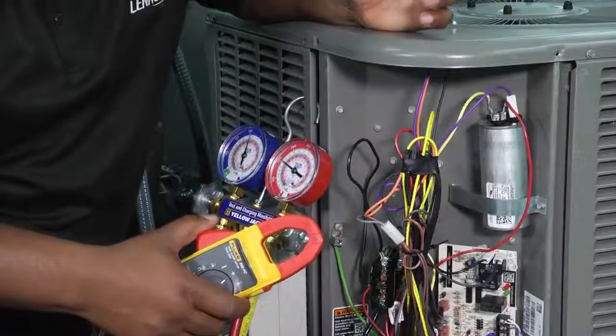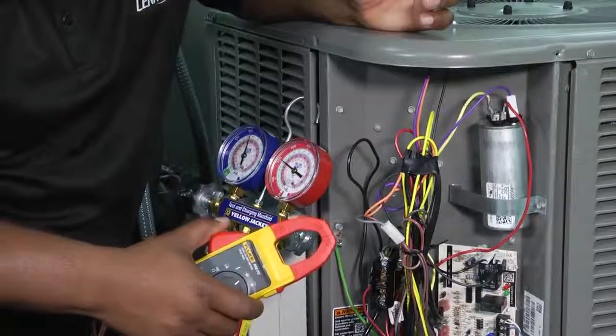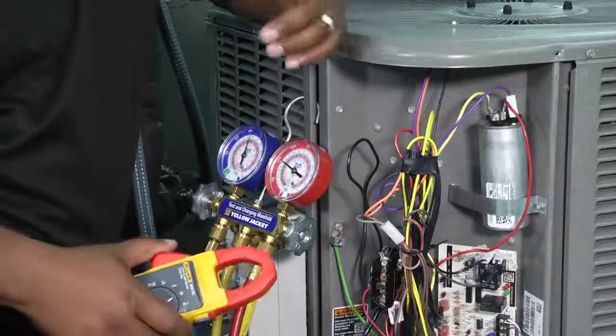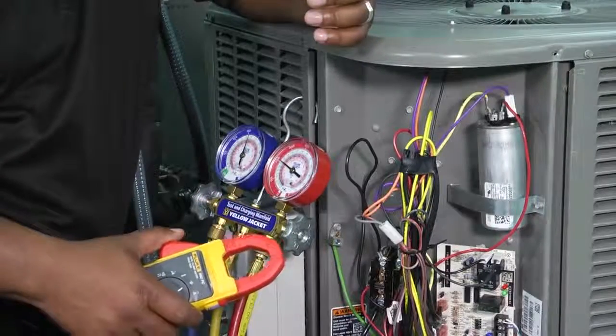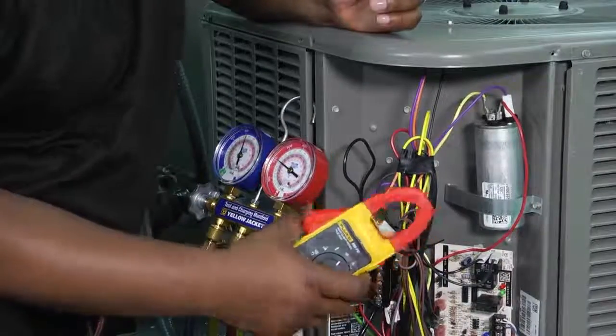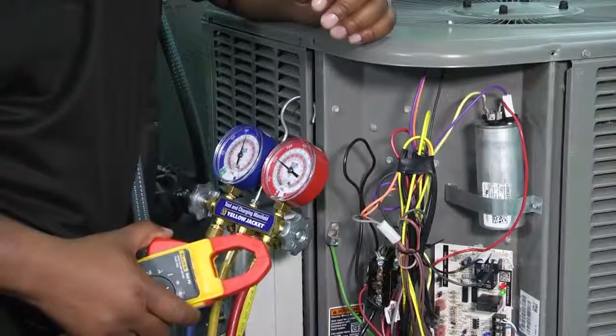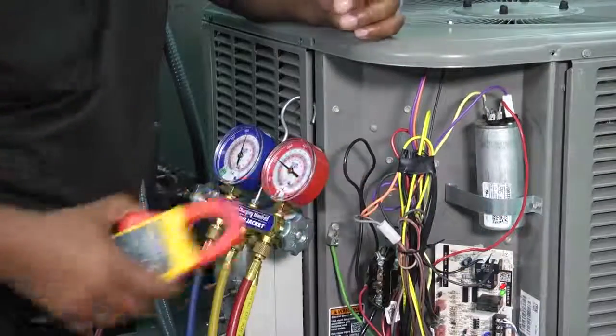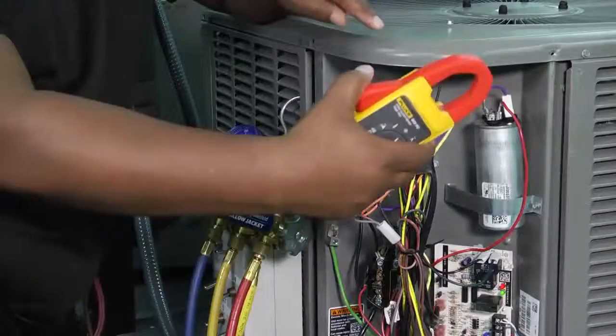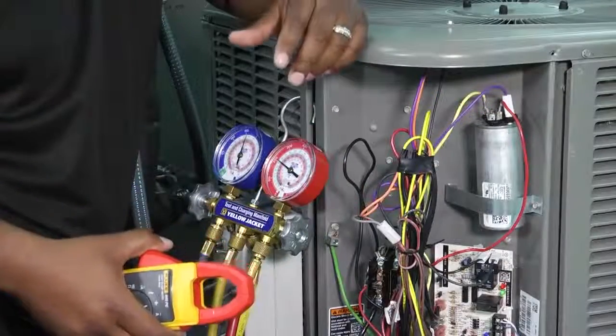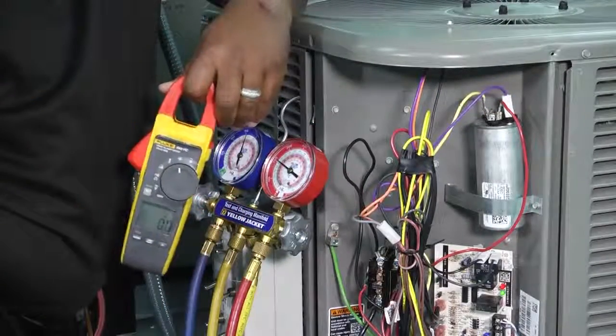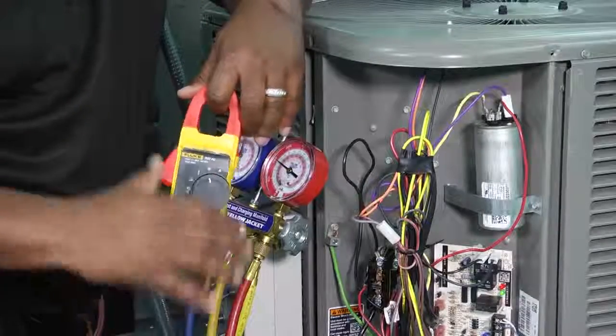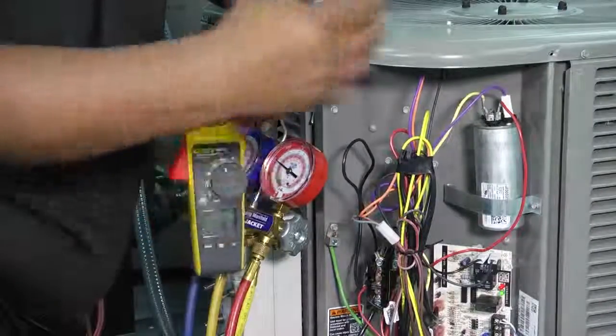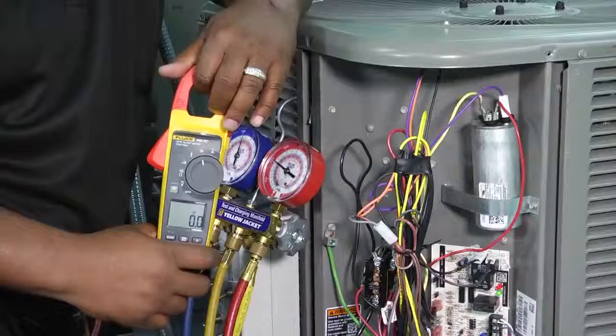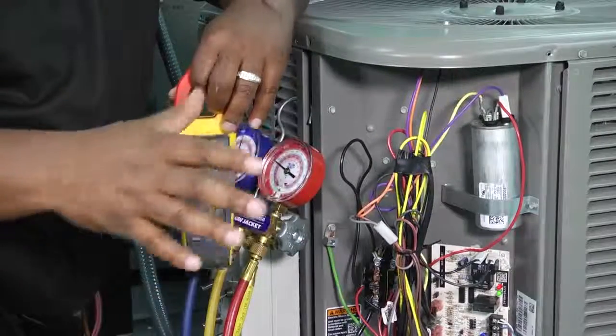draw on the capacitor, multiplying that amp draw by 2650, and dividing that by the voltage. You can also take a voltage on that capacitor. And if you look at the label, that voltage you'll be reading there, but you can take it while running and get an actual voltage. You do the math, which is 2650 times amps divided by voltage, and you'll get a capacitance reading there as well. So that way you can check it without ever disconnecting.